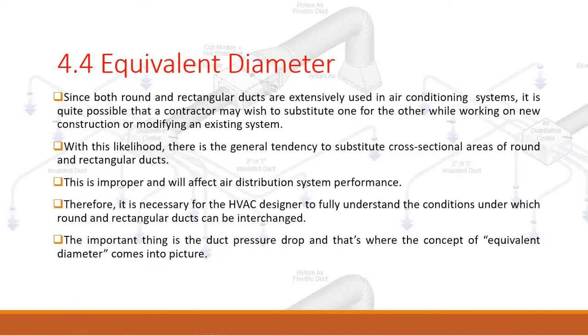Equivalent diameter. Since both round and rectangular ducts are extensively used in air conditioning systems, a contractor may wish to substitute one for the other during new construction or when modifying an existing system. There is a general tendency to substitute cross-sectional areas of round and rectangular ducts; this is improper and will affect air distribution system performance. Therefore, it is necessary for the HVAC designer to fully understand the conditions under which round and rectangular ducts can be interchanged.